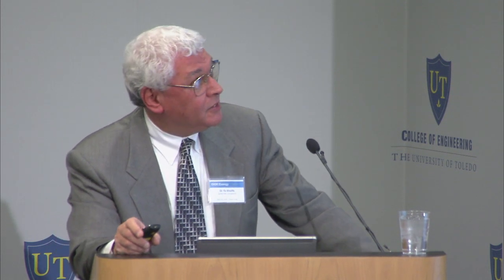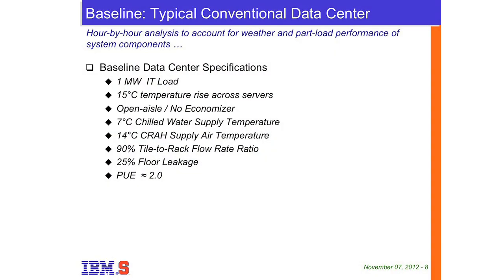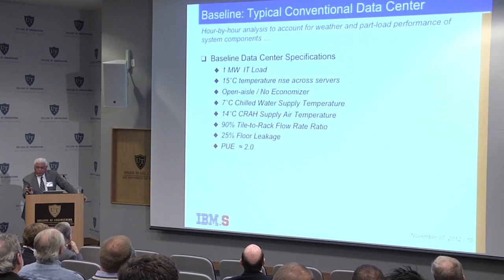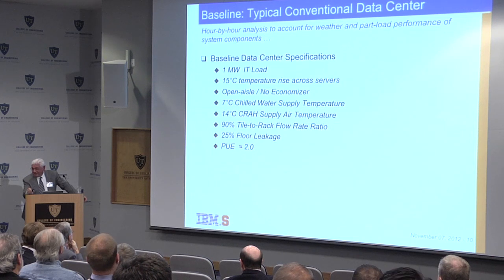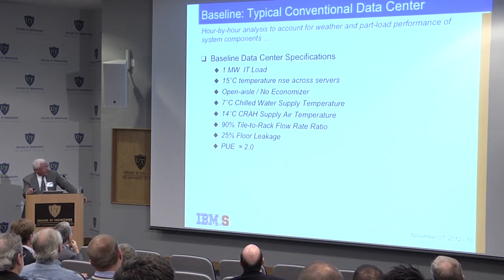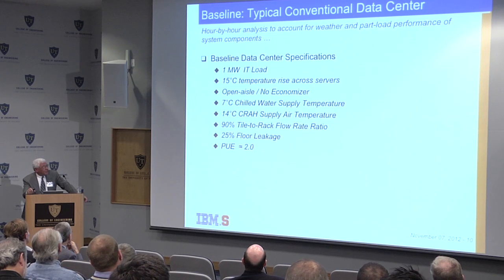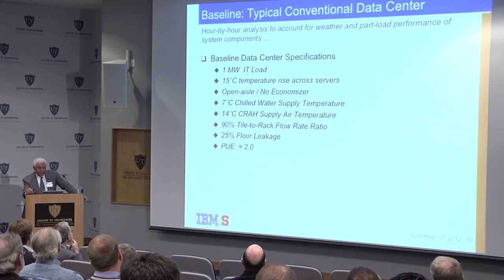We're going to compare everything to a conventional data center that looks like this: it has 1,000 kilowatts of IT load, cooled by a stream of chilled water with a 15 degree temperature rise across the servers. It's an open aisle with no economizer. The chilled water comes in at 7 degrees Celsius, typical if you're using a chiller, and the CRAC supplies air at 14 degrees Celsius. The ratio of flow coming out of the tile to the flow that goes through the servers is 90%, and there's 25% flow leakage outside, through cutouts or various leakage paths on the floor.